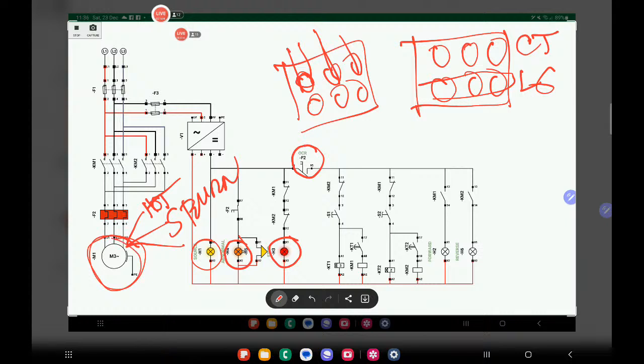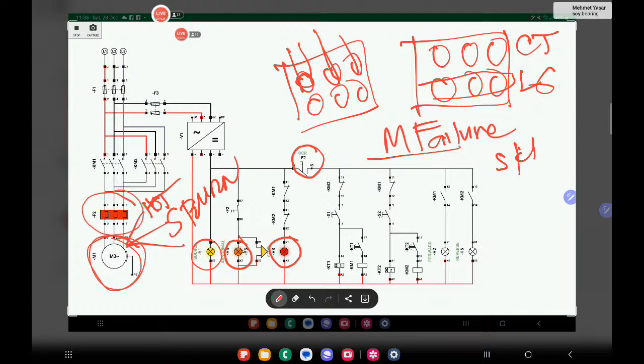If you can rotate the electrical motor by hand and it's freewheeling, you will know that it's not having a mechanical failure, right? Sometimes if your bearing is stuck, your motor will be overheating. You will have a high current and it will overload and activate your F2. So this would be the first thing that you need to do before you can do a test on your circuit, right?